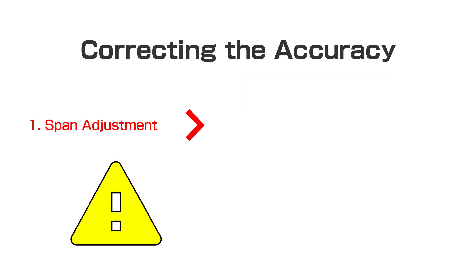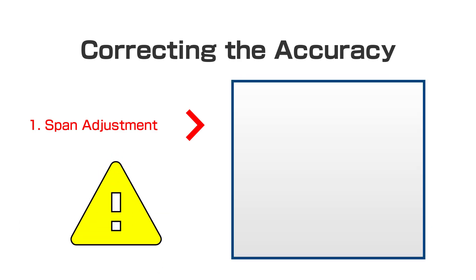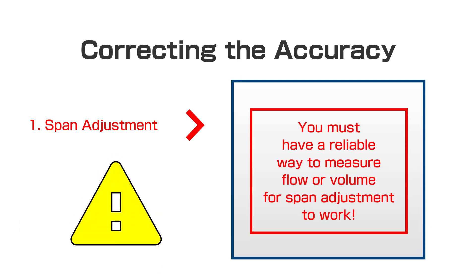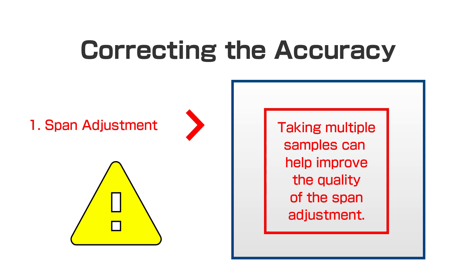One final note on this method: the quality of the correction is only as good as the quality of your flow rate or volume measurement. It might be a good idea to conduct multiple tests and average out your results to arrive at the best possible span adjustment value.